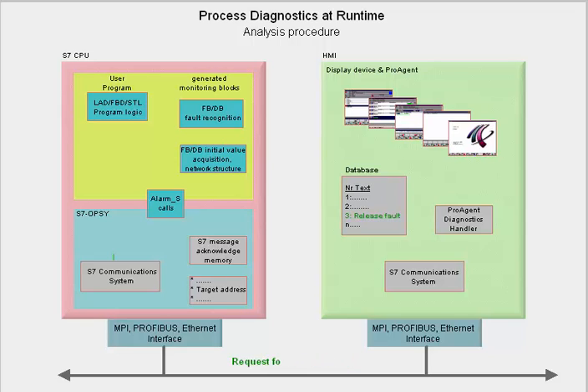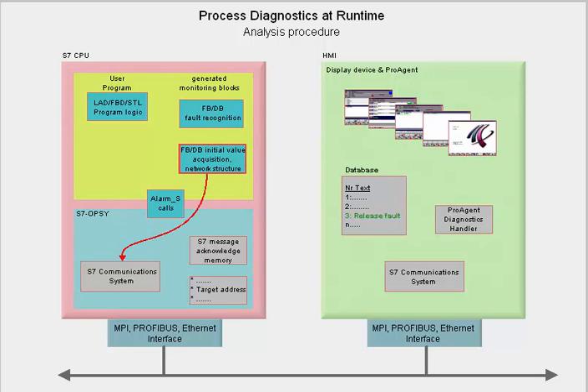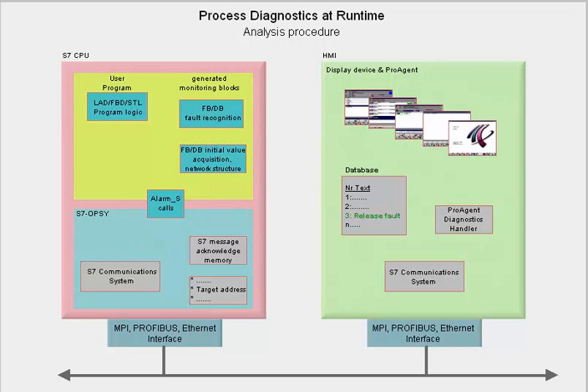From the relevant instance DB, the communication system of the target CPU takes the initial values of the status information which the addresses of the networks involved have at the time of the fault and the structure of the monitored network that is stored there. In this way, the system can then completely capture the addresses of auxiliary networks in which an interim result has been stored, a flag for example. This holds also for the case that these networks are in other blocks.